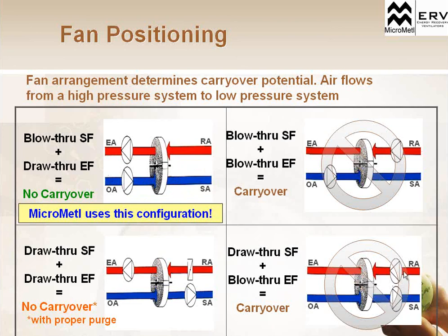If we had that push-through, pull-through design on the opposite, this second fan here is actually going to want to pull that exhaust air from the building around. So we want to make sure that we have a pull-through, push-through design, so we're getting all the exhaust air out of the building and maximizing that, or reducing the amount of leakage in the system.